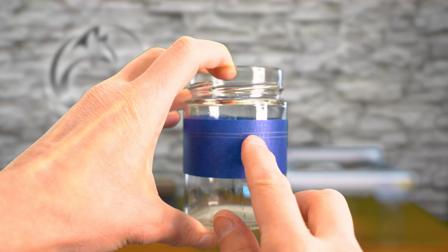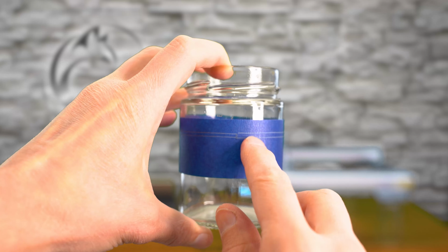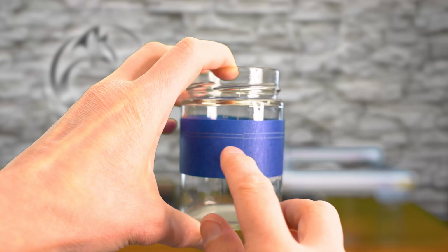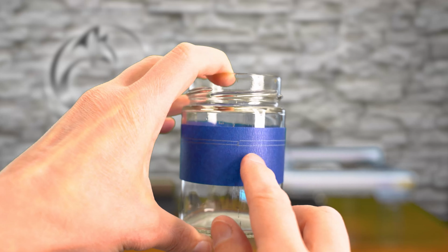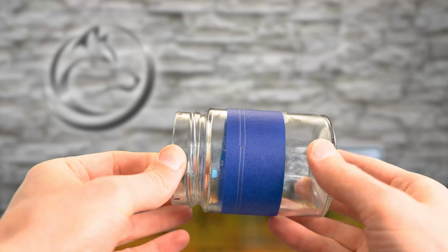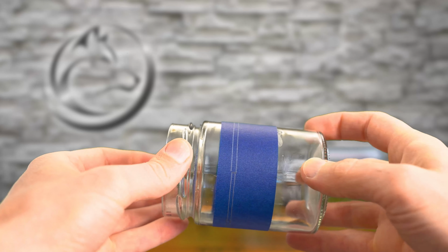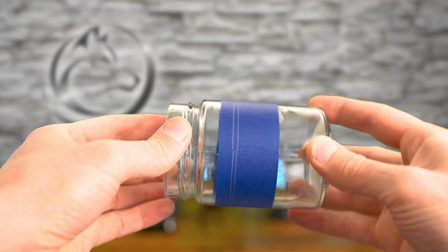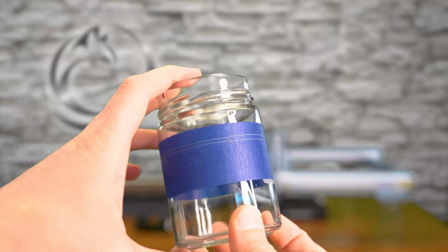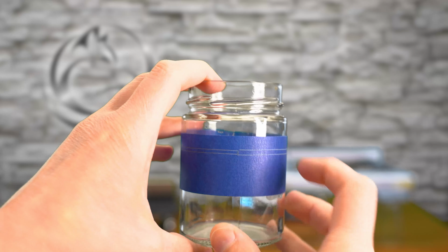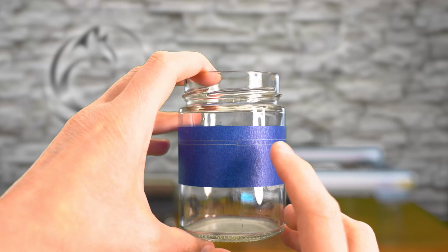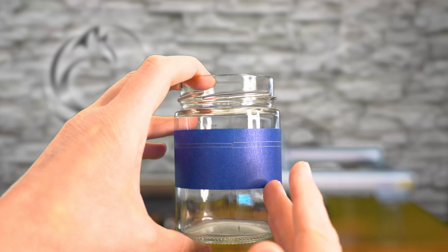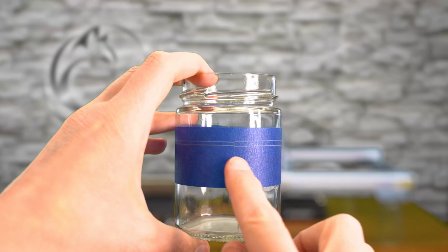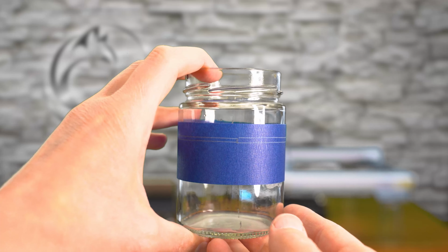We'll also see that there's a little bit of a width or height difference here on this side of the box versus the other side. And I found that when this runs this test, this tape builds up a diameter and it allows this to rock back and forth. And when I do this calibration test, this is very common that I see and is perfectly normal. But know that when I do an actual engraving, I don't see this phenomenon at all.